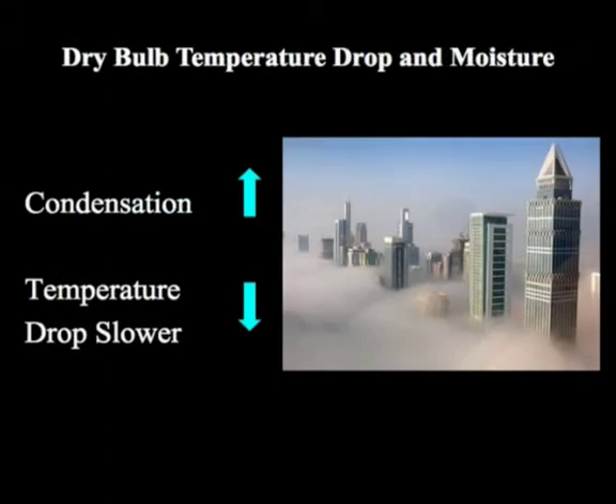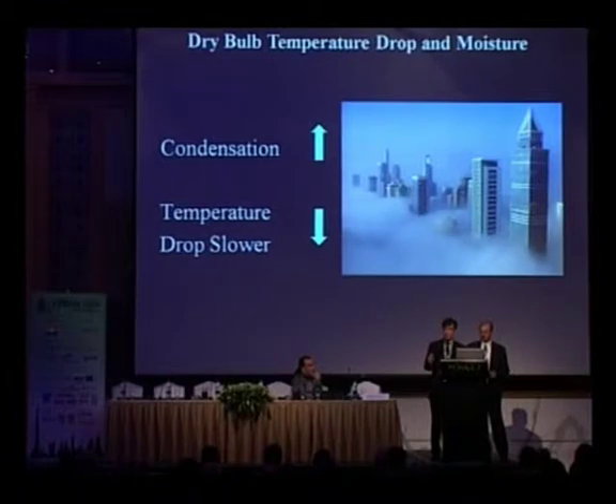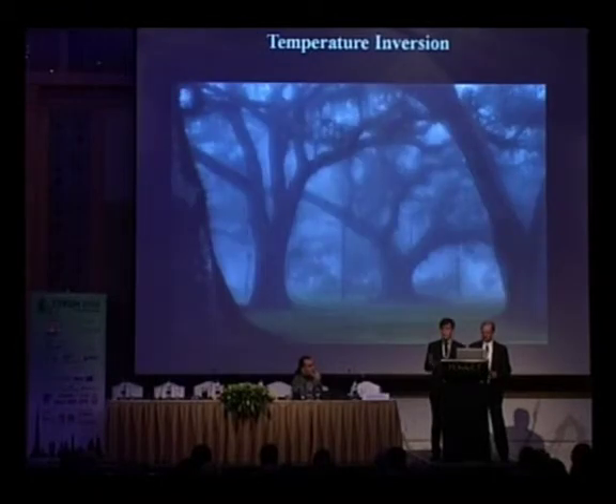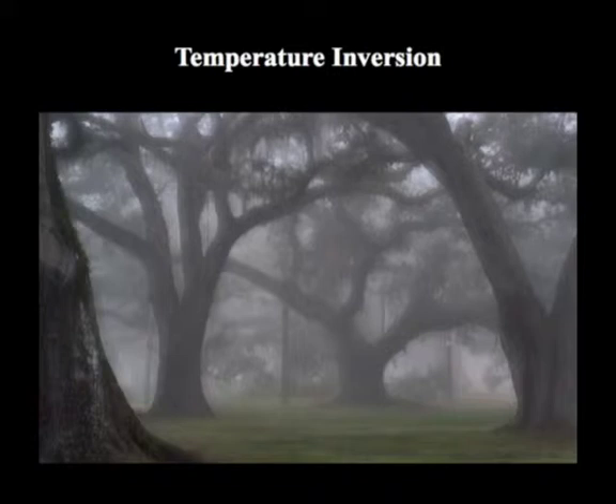The reason for the difference between the two temperature drops is moisture content in the air. Many of you who woke up this morning will have found the outside is kind of moist. Whenever there is high moisture in the air, as temperature drops, moisture tends to condense. When it condenses, it releases heat, and that's why it offsets that dropping temperature effect. Now, for those who are involved in construction, you may want to take that as a VE item, right? Size the cooling plant on the taller part of the building with a lower design temperature. You have to be careful because there are temperature inversions, like what we experienced this morning. The ground is actually condensed and forming clouds.